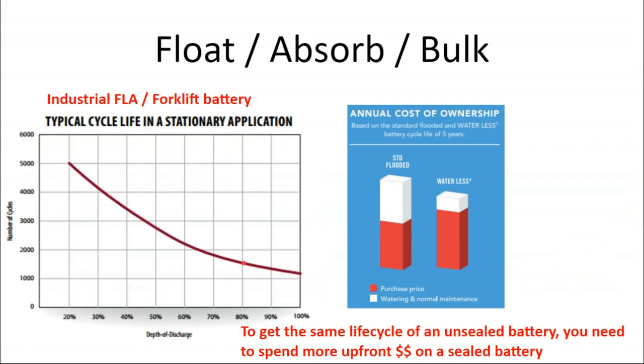Even though a sealed battery is nice because there's no maintenance involved, an unsealed battery can have better value because the maintenance isn't that big of a deal. You get the ability to power condition the battery for longer life, and less degradation from rapid charging and discharging. So unsealed batteries cost less and last longer than sealed batteries, which is why within lead acid, I'm much more a fan of unsealed than sealed.